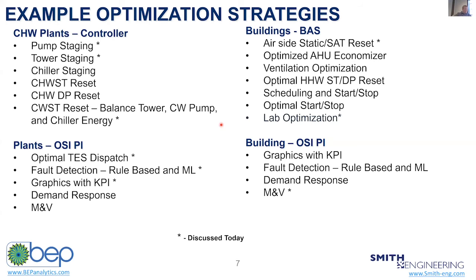So here's some examples of these strategies. I want to give some examples of strategies on the chilled water plant side that should be done in the controller, the building side that should be done in the controller, and then some examples of things that should be done in an analytics engine. So simple things such as pump staging, tower staging, chiller staging, chilled water supply temperature reset, chilled water DP reset, condenser water supply temperature reset. Some of these could be done in an overlay optimization platform, but they can also be done within the controller.